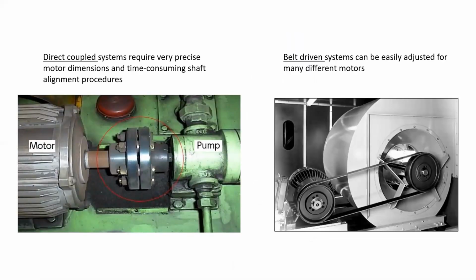Case in point are these two motor installations that we have. On the left is a direct coupled system, which requires a very precise motor dimension and an extremely accurate and time-consuming shaft alignment procedure. The motor installation on the right is very common for HVAC and air ventilation systems. It can be easily adjusted for many different shapes and sizes and brands of electric motor because it's on a belt-driven system with pulleys. If I have a larger or a smaller motor, all that I need to do is slide the motor towards the housing or further away from the housing, and there are then bolts to secure it down. I can use different sizes of pulleys to adjust the speed, and I can also get different sizes of drive belts.